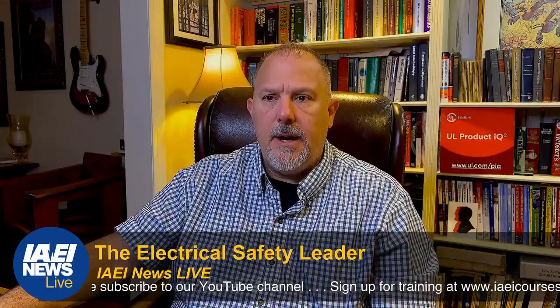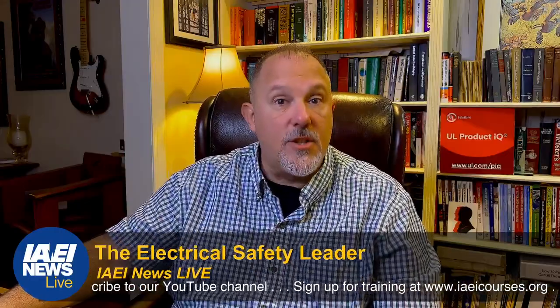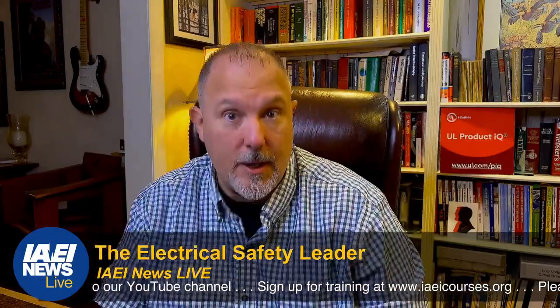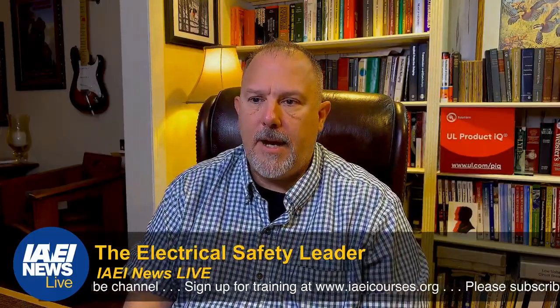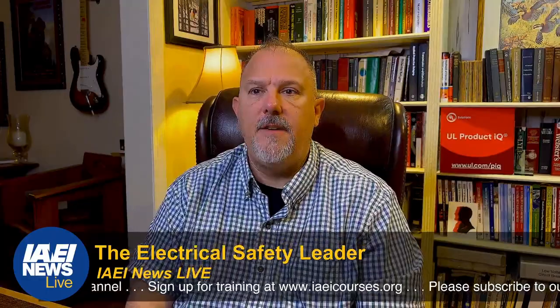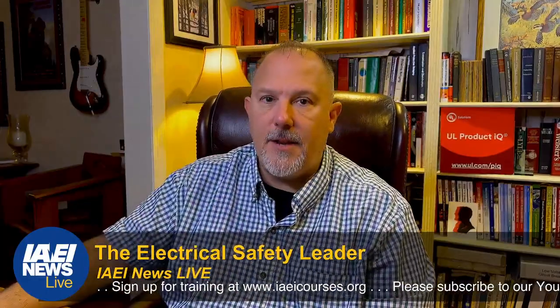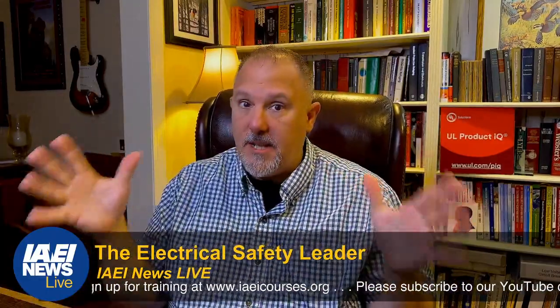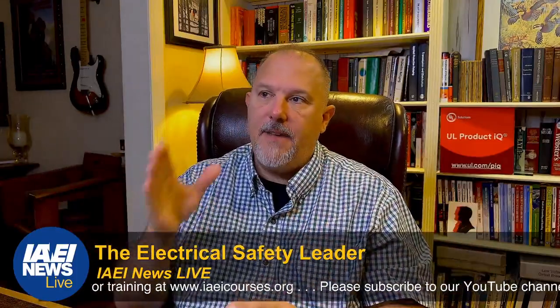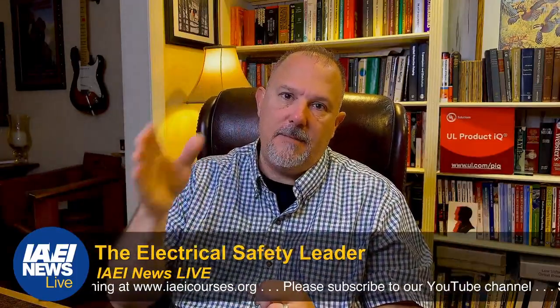210.11 will tell me I need to have a branch circuit, a 20 amp branch circuit going to that bathroom. I only have lighting requirements, and I'm going to have switching requirements for that light in the bathroom. So remember, we're in the basement, but I have a defined space in my basement.